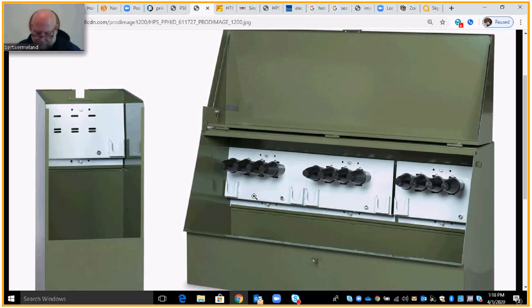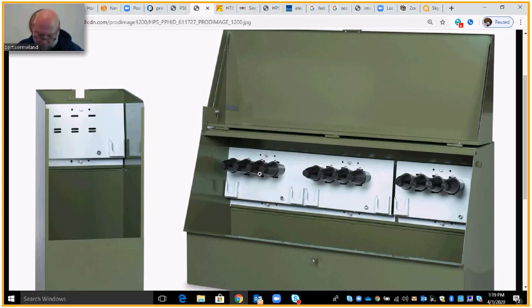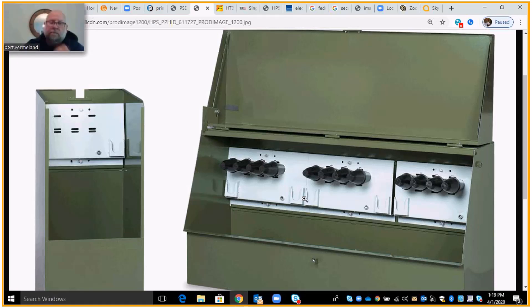They are not labeled. The question was how these are labeled — well, there's no labeling on them. No number one, two, three, four, and no A, B, or C when you first get the three-phase enclosure. That is a rule of the industry: A always goes on the left, B in the middle, C on the right. That's what you do inside meter bases, three-phase enclosures, and transformers when we get to the three-phase transformer as well.